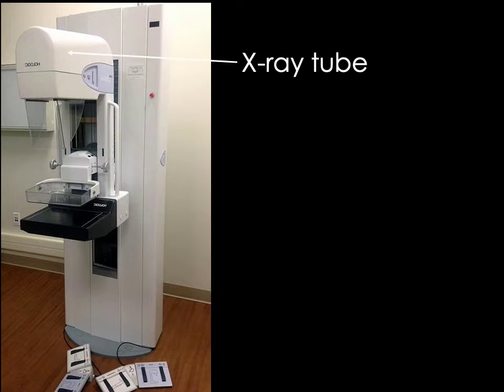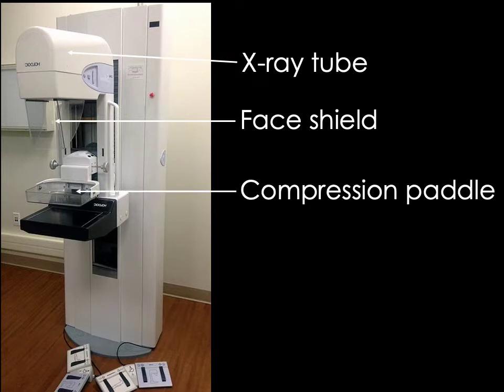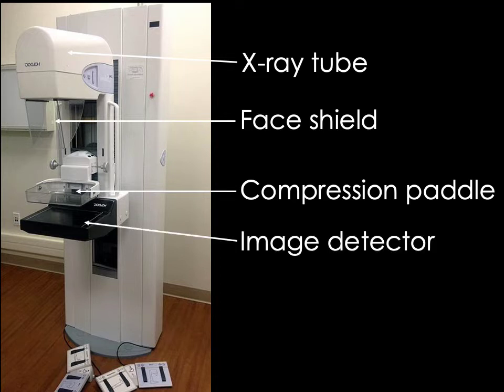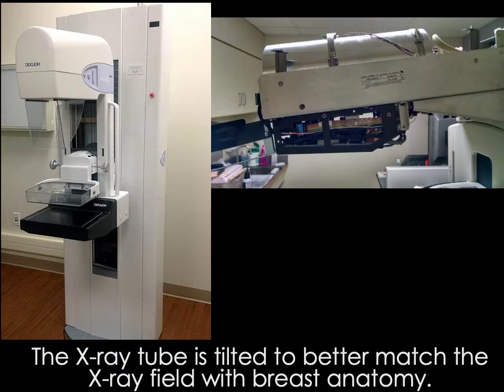The first component is the x-ray tube, located in the upper part of the machine. Next is the face shield, a plastic piece used to keep the patient's head and neck out of the imaging field of view. Then we have the compression paddle, which is raised and lowered to adequately compress the patient's breast. And finally, there's the breast support, which lays over the image detector — a digital detector in this system. One thing to note is that the x-ray tube is at an angle, done to better match the x-ray field with breast anatomy.